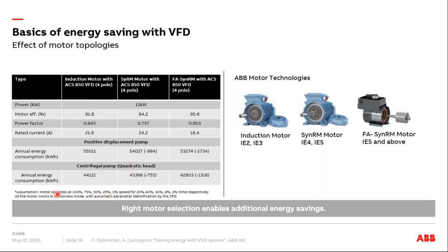Some of the assumptions here are about how the motors are operating. At 100% load, we are operating 20% of the time; at 75% load, 40%; at 50%, 25% load, we are operating for 30% of the time. So basically it creates a load cycle for these different motor drive packages.